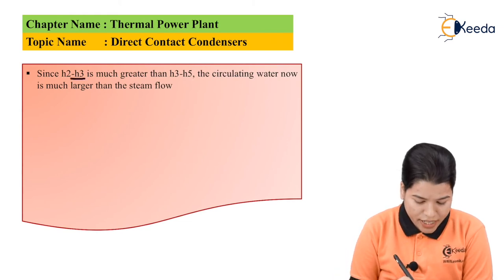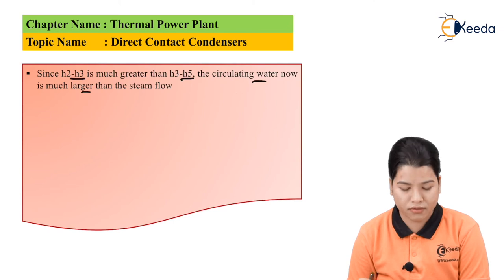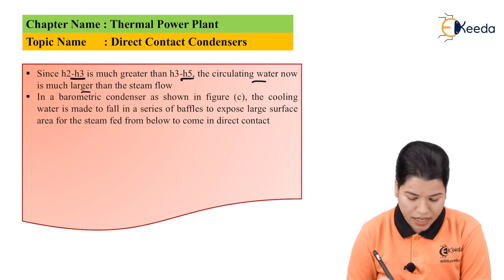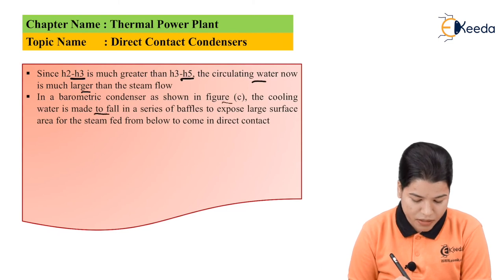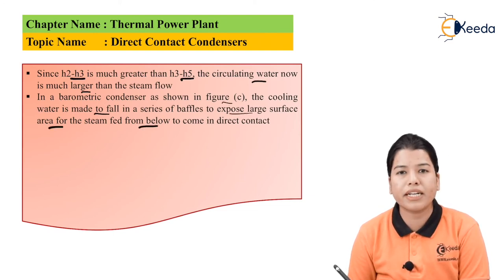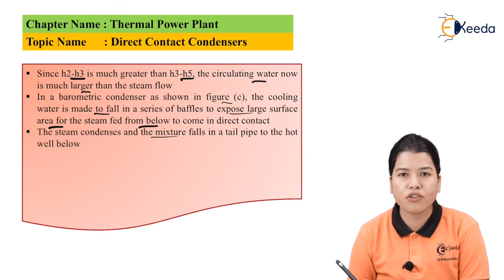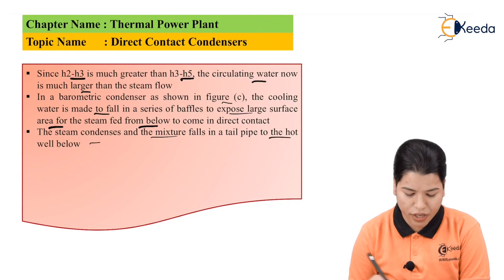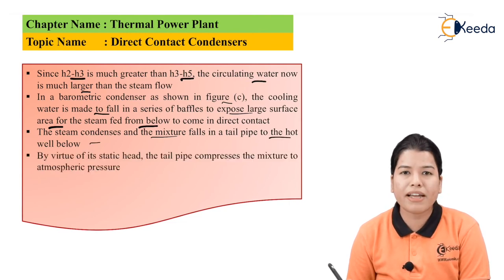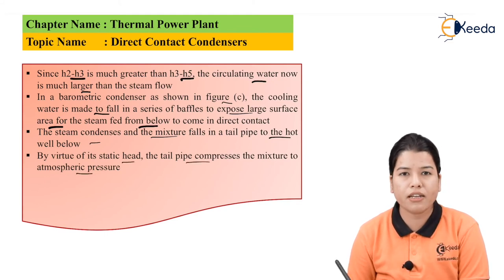Since h2 minus h3 is much greater than h3 minus h5, the circulating water flow is much greater than the steam flow. In the barometric condenser, as shown in figure C, the cooling water is made to fall on a series of baffles to expose a large surface area for the steam, which is fed from below to come into direct contact. The steam condenses and the mixture falls down the tail pipe. By virtue of this static head, the tail pipe compresses the mixture to atmospheric pressure.